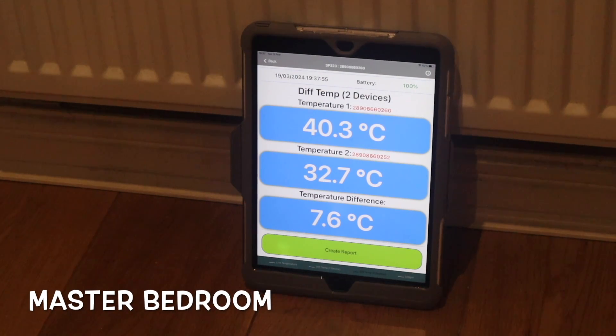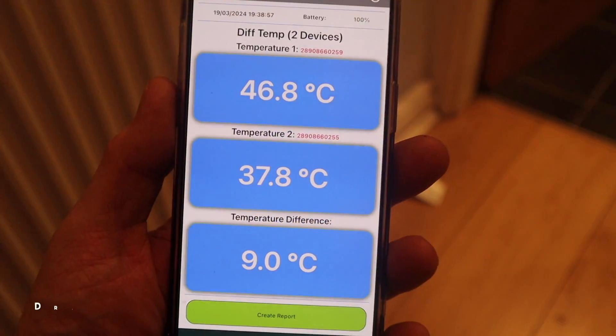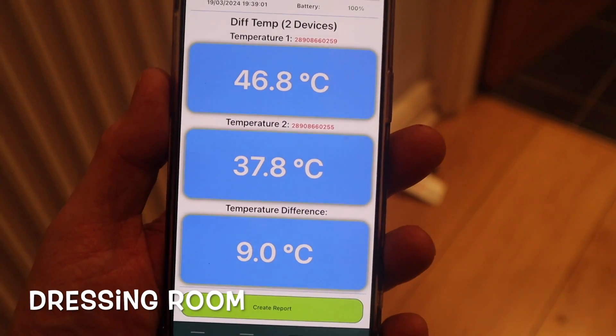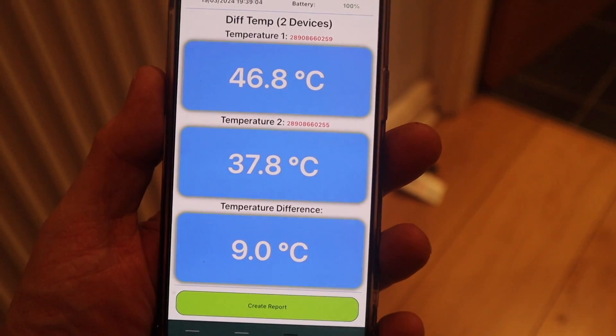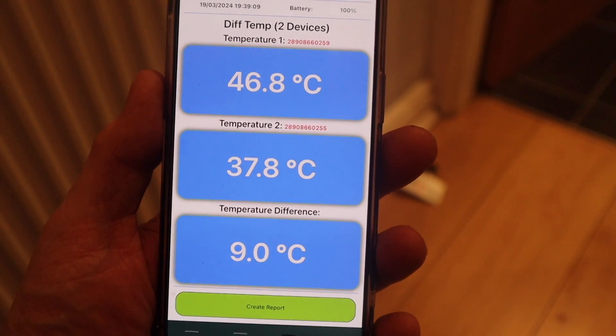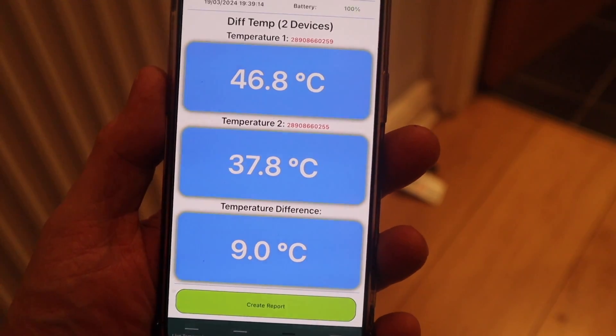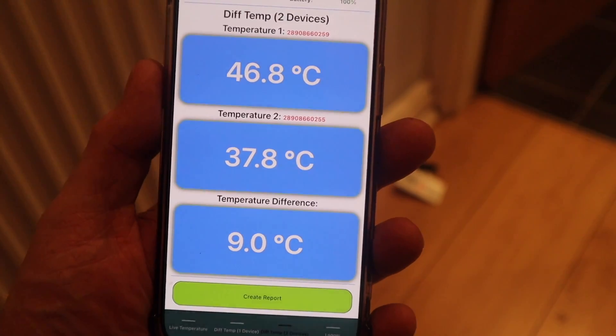We seem to be pretty stable now. This radiator is showing 40.3°C on the flow, 32.7°C on the return, a difference of 7.6°C — and remember this is the last radiator on this circuit. In the dressing room, we've got a flow of 46.8°C, return of 37.8°C, with a difference of 9°C. So there's not that much difference in the delta T between flow and return, but there is quite a difference in the actual flow temperatures.